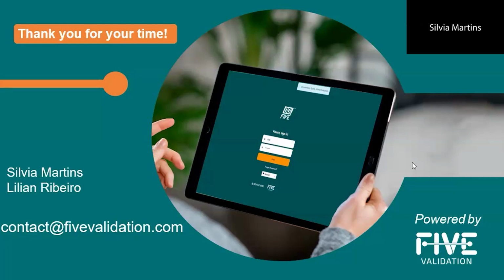Okay, it's a great question. And actually, I'd like to finish this webinar with a great discussion here because it depends. So a CDS with very standard functionalities, in our opinion from Pharma validation, we would classify as category 3. However, sometimes we use a CDS system to include, for example, custom reports or custom calculations and to eliminate some spreadsheets that are not desired for us to have there, because companies usually have a high cost to keep this kind of system, and the current CDS are very good, and they can embrace almost 100% of the Excel spreadsheet calculations that your routine demands.